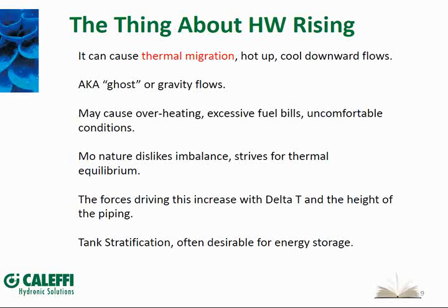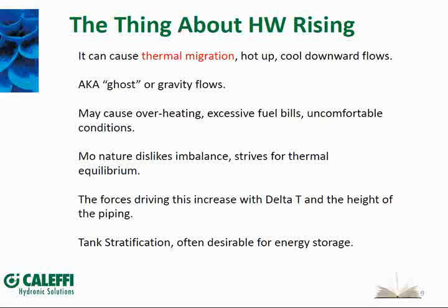Nature dislikes an imbalance. If there's a cold pocket of water and there's a belly full of hot water down in the boiler, they're going to try and equalize — going through valves, through fittings, doing whatever they can to equalize that temperature difference. What drives it is the temperature difference: the greater the delta T, the more potential for thermal migration.